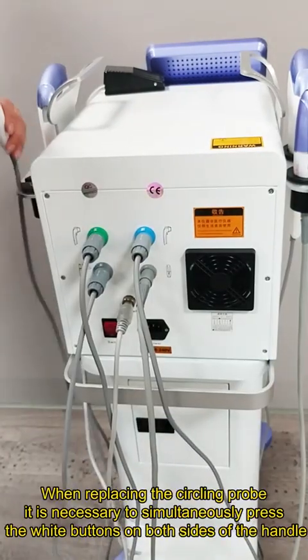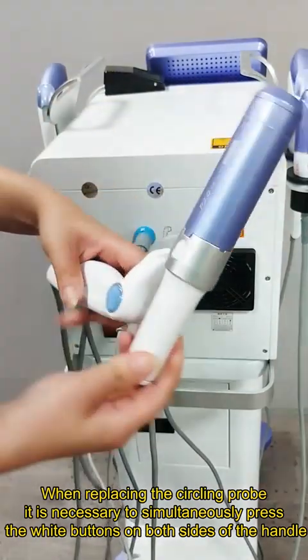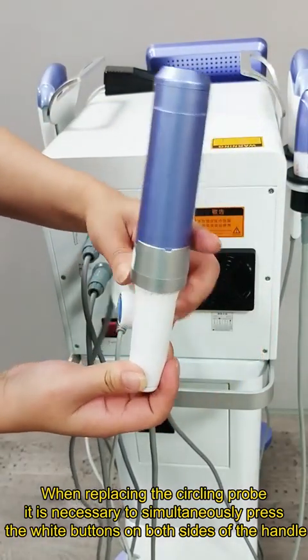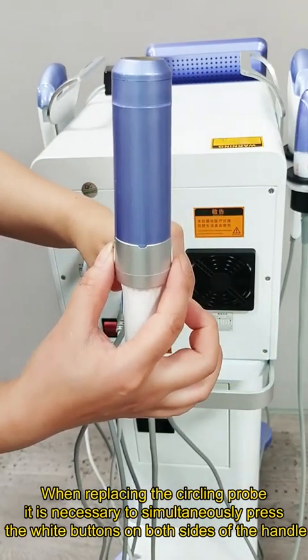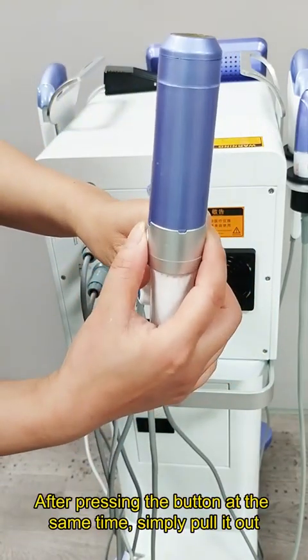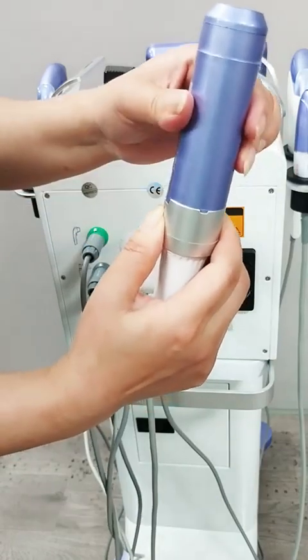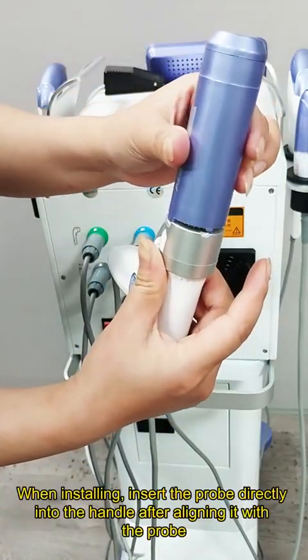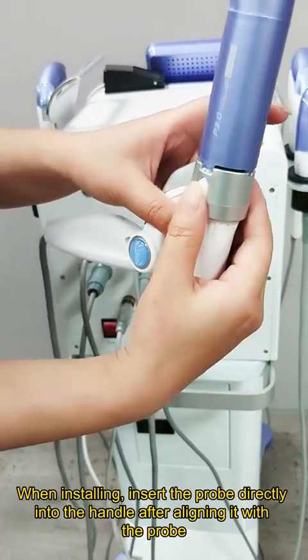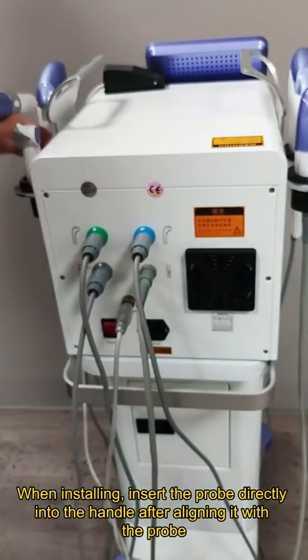When replacing the circling probe, it is necessary to simultaneously press the white buttons on both sides of the handle. After pressing the buttons at the same time, simply pull it out. When installing, insert the probe directly into the handle after aligning it with the probe operation tutorial.